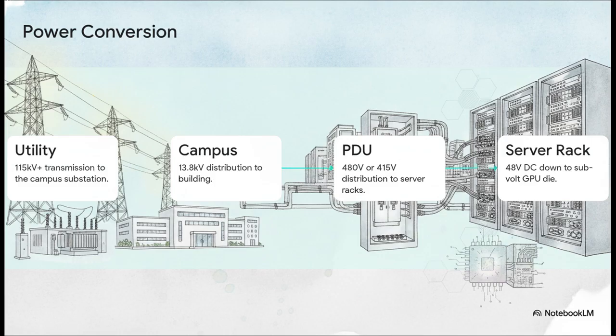Power doesn't just flow straight from a power line into a computer chip. It undergoes at least 7 conversion stages before it does any useful math for us. It steps down from massive 115 kilovolt transmission lines at the utility level, down to 13.8 kilovolts at the campus substation, then to 480 volts at the building's power distribution units, or PDUs. Then it hits the server racks, converting to 48-volt DC, before finally stepping all the way down to sub-volt levels right at the GPU die.